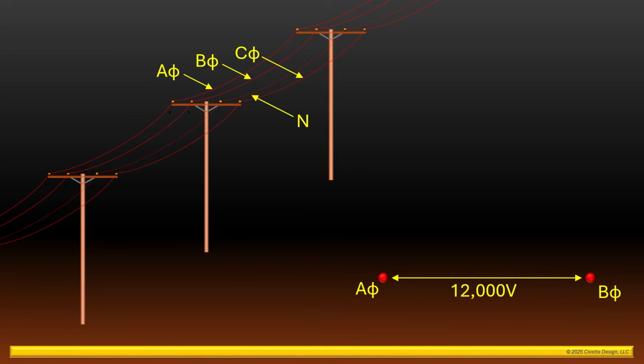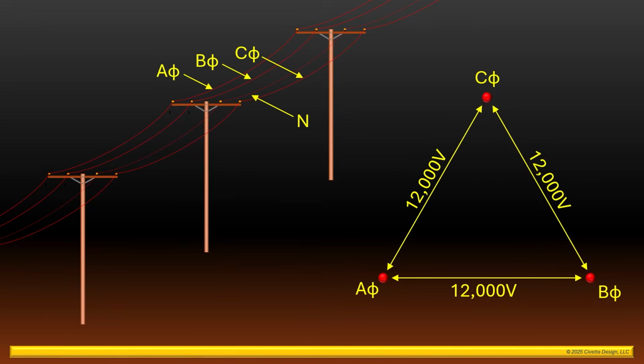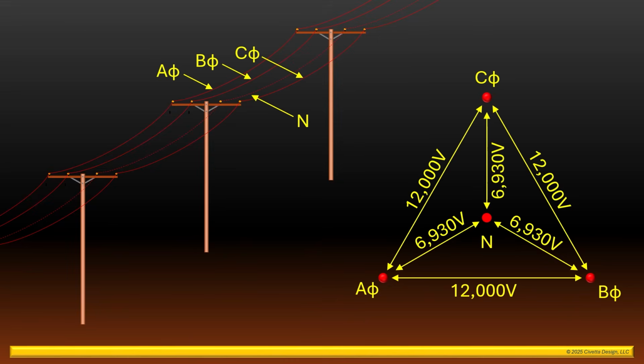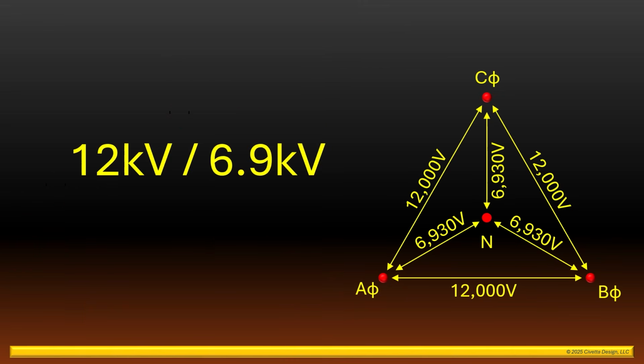A typical 12,000 volt primary system is described that way because the voltage potential between any two of the phase conductors is 12,000 volts. Between A and B phases, A and C phases, or B and C phases, all 12,000 volts. The voltage potential between any of the three phases and the neutral conductor is 6,930 volts. These primary voltages are often abbreviated as 12 kV and 6.9 kV.